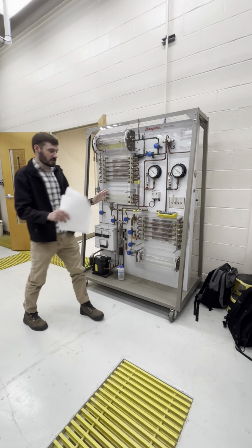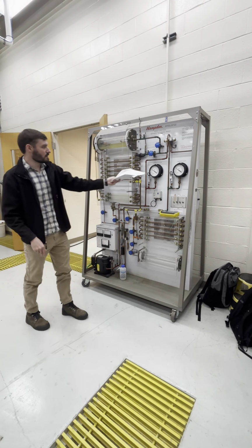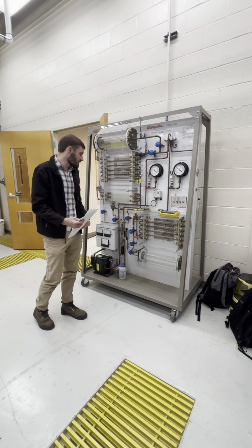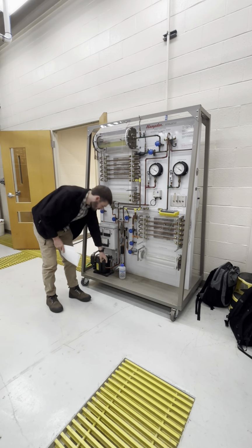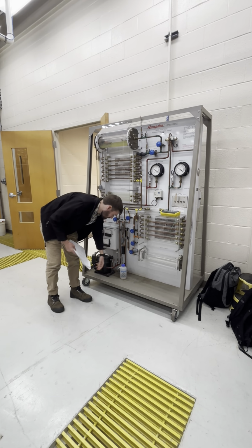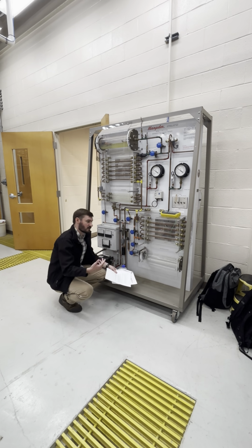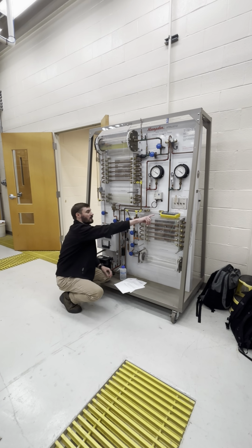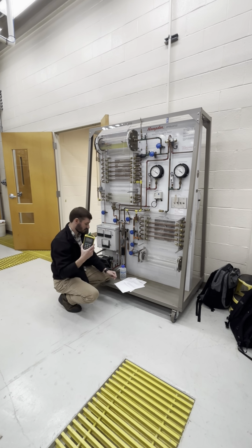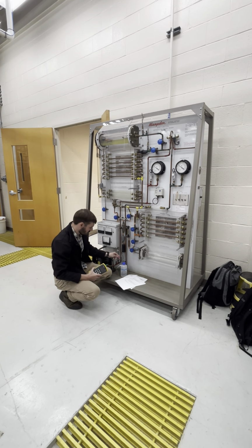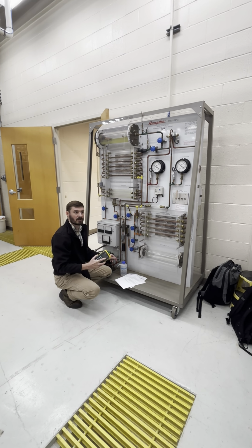Okay. Eventually, you get to steady state, and you measure those two, and then you're going to start taking temperatures on either side of those components I mentioned earlier. So they have these little temperature wells. You're going to fill them up with water, just so we have some kind of heat transfer fluid. You can take your temperature data logger, put the thermocouple inside, and just wait for it to steady out, and log it.